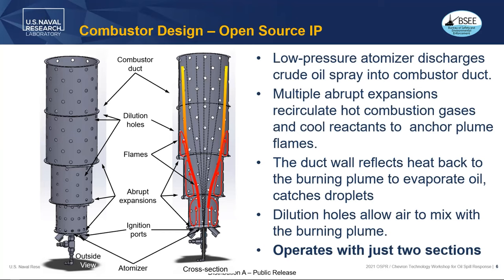Dilution air passes through holes in this shroud, which gets quite hot so that as air passes through it, it heats up and assists in the evaporation and burning process. The diagram shows four sections, but we've discovered we can operate with very stable and clean burning using just two sections. The extra two sections actually inhibit entrainment of air and mixing with the plume, making a dirtier flame.